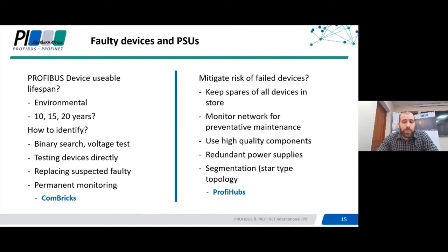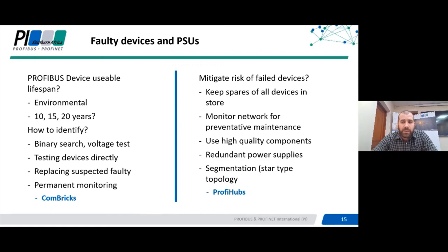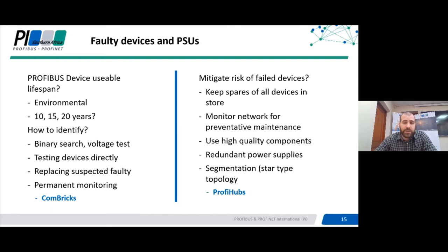Ensure that you keep spares in store for all components within your plant, especially devices reaching 10 to 15 years of age — replace components identified as sensitive and prone to faults. You can use the binary search for a constant fault; older devices with a failed ASIC may create a short on the A or B lines. You can also test devices directly using a master simulator device — plug it straight into your bus testing tool, get the device online and you'll see if it's behaving as it should, helping you isolate problems per device. For severely intermittent faults you can install a permanent monitoring tool, such as Combricks, which acts like a bus monitor but permanently monitors and keeps a log or history so you can log in at any point to investigate issues.